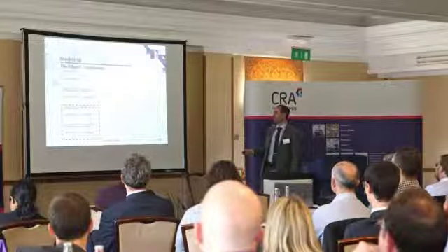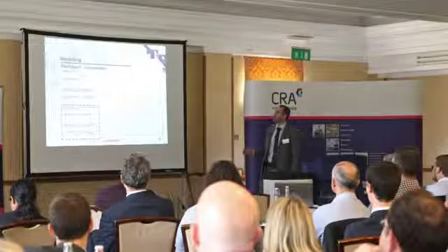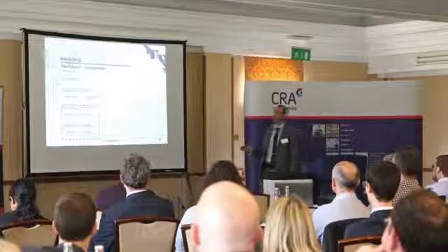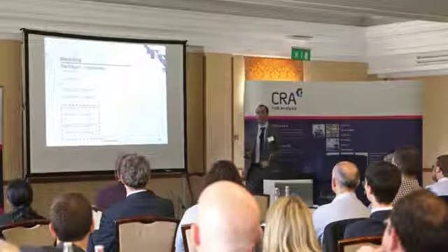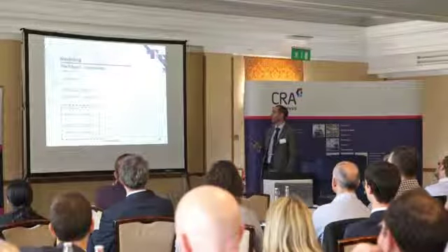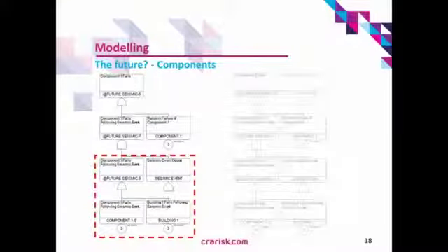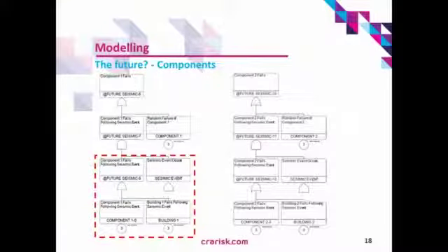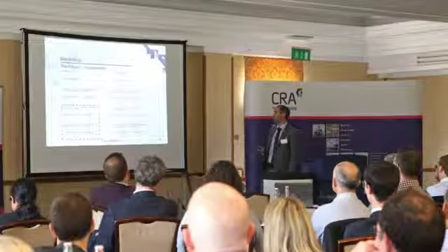So the smart ones amongst you will notice there'll probably be a magical level by which you'll have an even distribution between your seismic and random failures, but generally you will see it will shift quite sharply depending on your level of seismic event. And you can copy and paste that over however many components you've got in your train and combine it under whatever combination logic is appropriate for your system. So for a 2-train system, you would be doing this under AND logic.